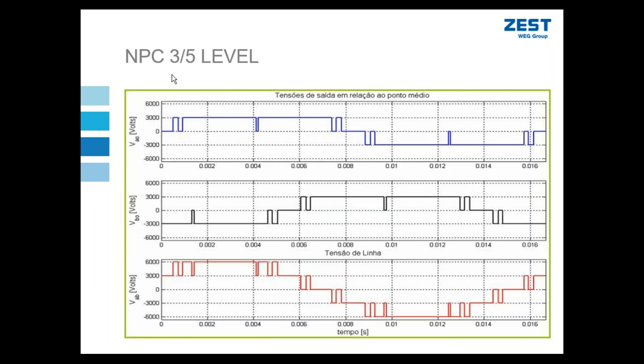So why it's called an NPC 3 level is I'm able to create my three levels. Remember, this is phase to phase. I can now have a phase to phase, I'm actually five levels. Let's just go back a little bit. Let's just talk about these levels. We normally define a topology by its number of levels in the phase to neutral case. Those number of levels always increases in the phase to phase case.